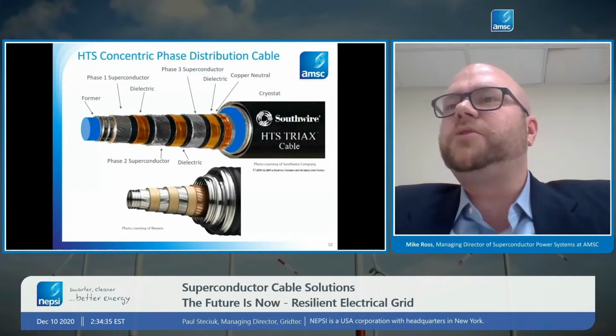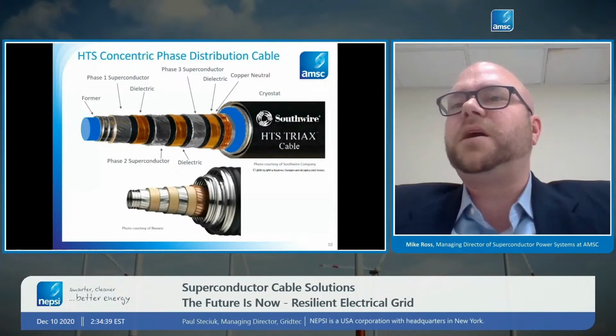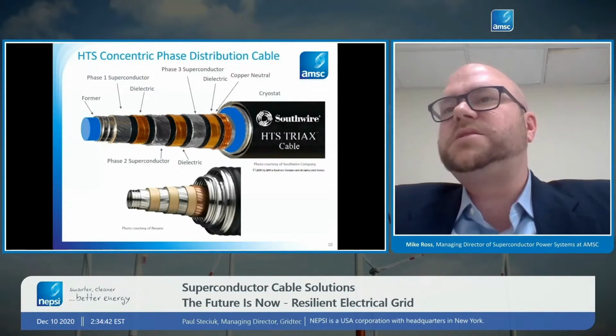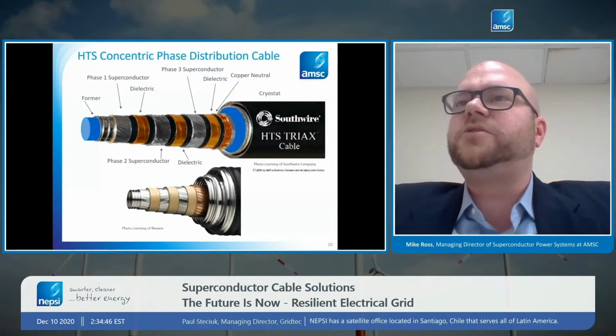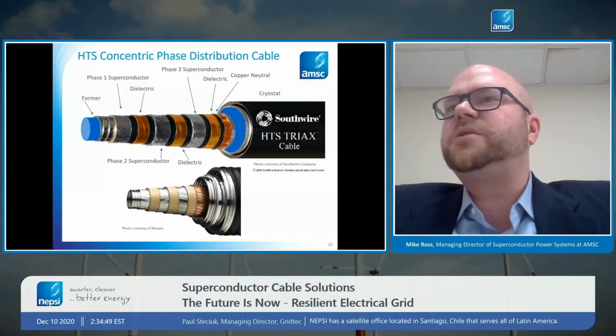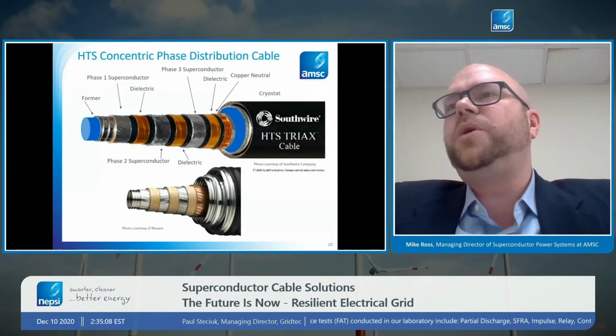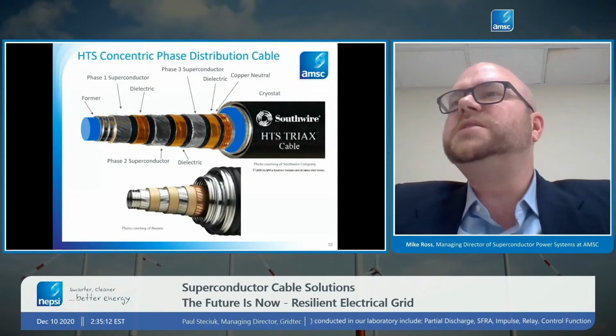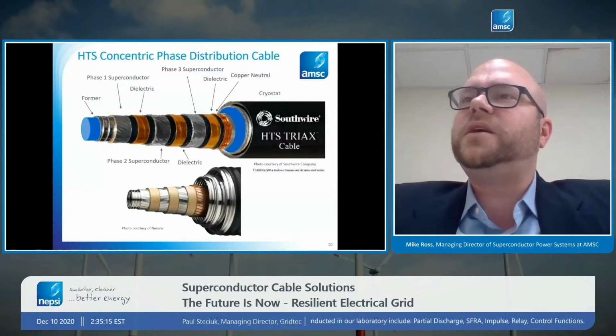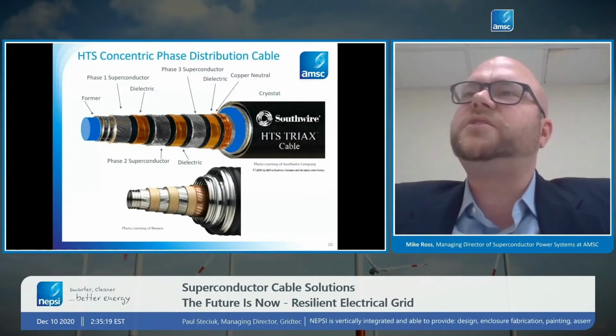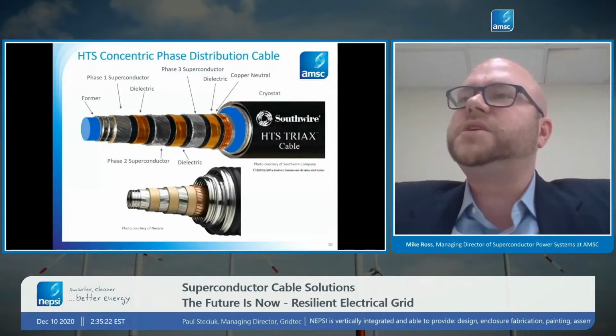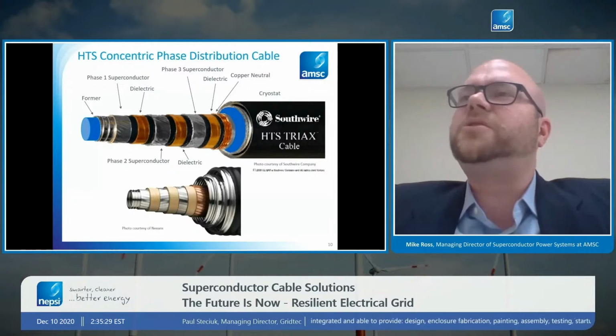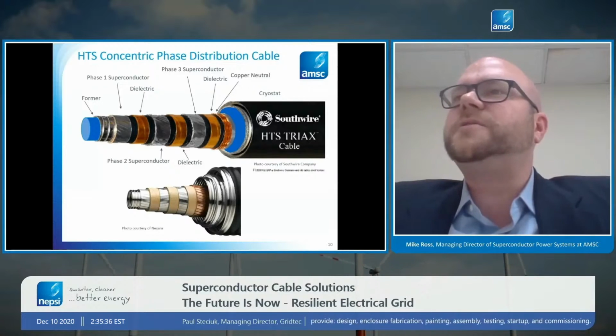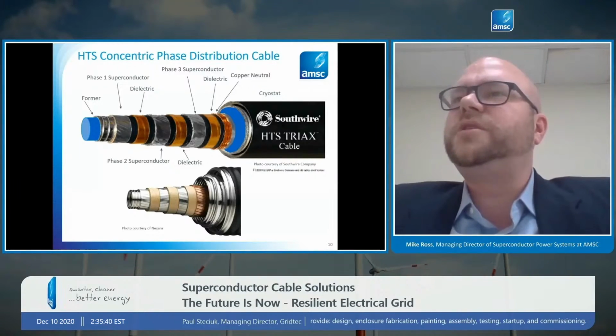What we're looking at here is two different cables by two different manufacturers. The top one is from Southwire. The lower one is from Nexans. In both cases, they're using American Superconductor material. You can see that the configurations are generally the same with some differences. What we're looking at here is a cable that goes inside what we call a cryostat. On the right-hand side, you can see a cryostat, which is a double-walled stainless steel tube, and between those two walls is a vacuum. Just like a stainless steel travel coffee mug, that's the same concept. You have two layers of steel with a vacuum in between, and that vacuum creates the thermal insulation for us to move our cold liquid nitrogen through the cable.